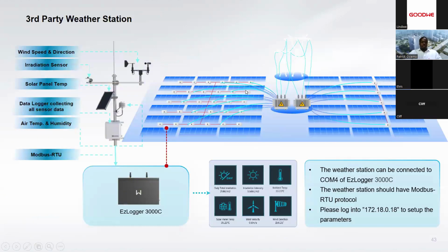Now, similarly, the GT series is capable, when integrated with the EasyLogger 3000C, of integrating third-party weather stations and monitoring the performance ratio of your plant. Now, as long as the third-party weather station communicates with the Modbus RTU protocol, the compatibility can be established. And in this sense, you're able to monitor the irradiance, temperature, wind direction, wind speed, all the particulars, specification that your weather station is able to display. Now, this is a major topic in terms of performance ratio monitoring of the PV plants.